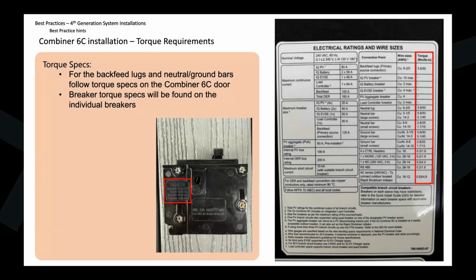And we send out a field service tech. They do a thermal imaging camera scan before they start. They see where the issues are coming from. And I get it, it's end of the year and everybody's pushing as fast as possible to finish installs, but we're seeing 2 to 3 turns on a screw, either on the combiner's main lugs or even on breakers themselves. So I know all of us say, oh, I've been doing electrical for years. Well, I've got to tell you, we've been seeing them.